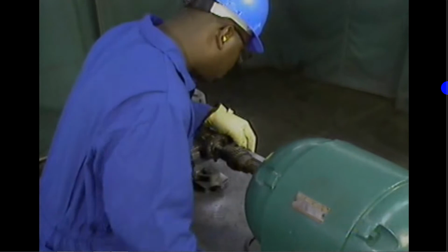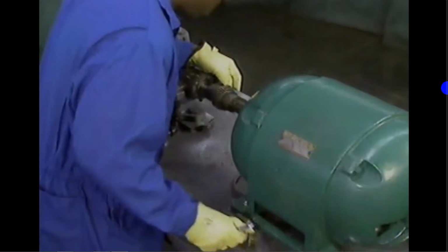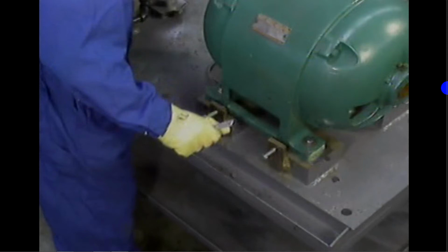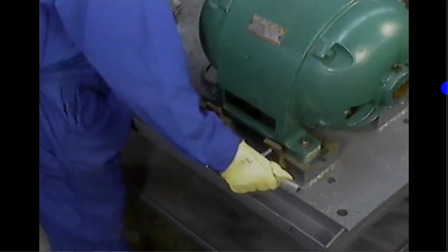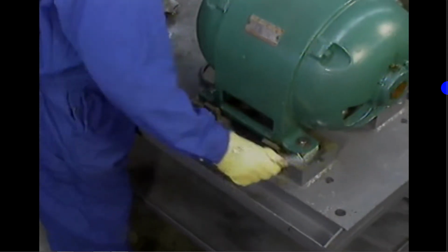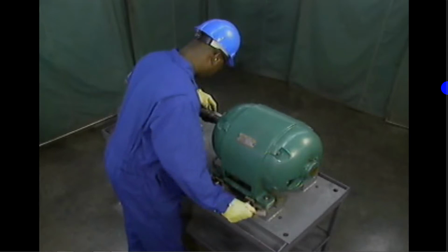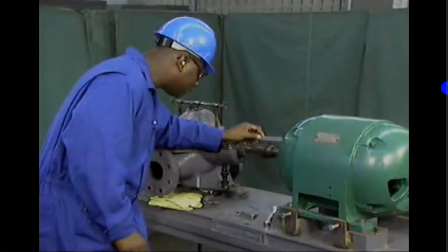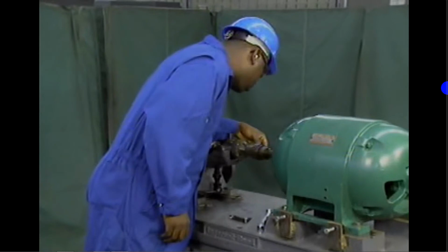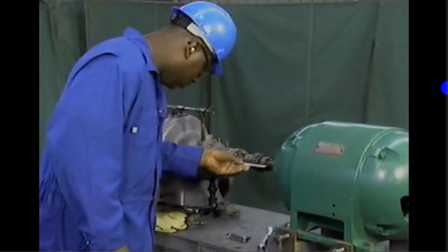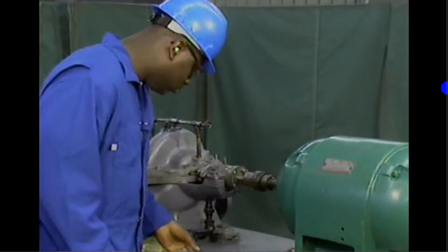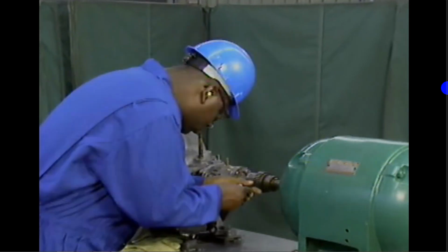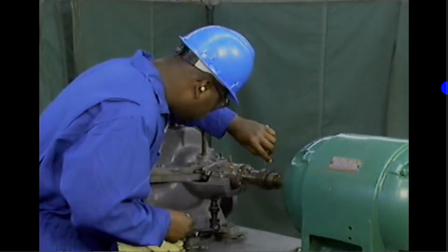To correct the misalignment, the mechanic uses jacking bolts to shift the motor towards 3 o'clock. Because of the angular misalignment, he shifts the back end of the motor more than the coupling end. As he shifts the motor, he continues to check the alignment of the couplings. When he finishes aligning the shafts in the horizontal plane, he rechecks all of the measurements to make sure that he didn't disturb any of the previous adjustments. He also double-checks the face gap to make sure that it's still within the coupling manufacturer's specified range.